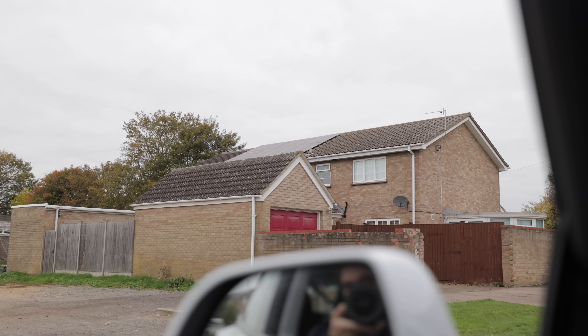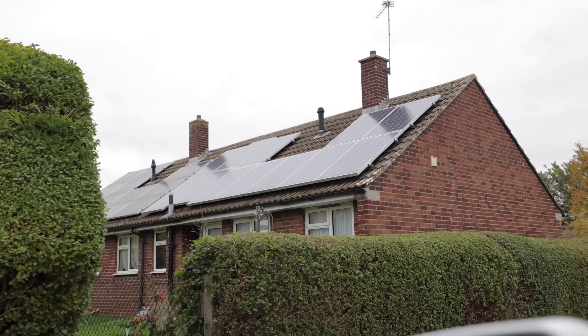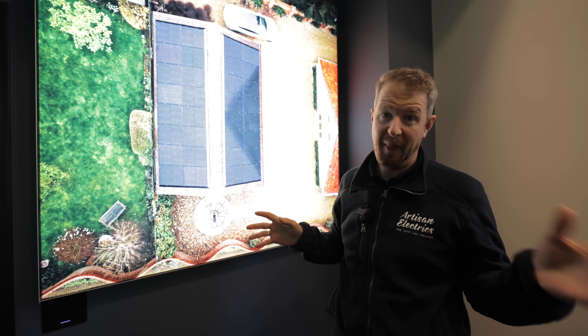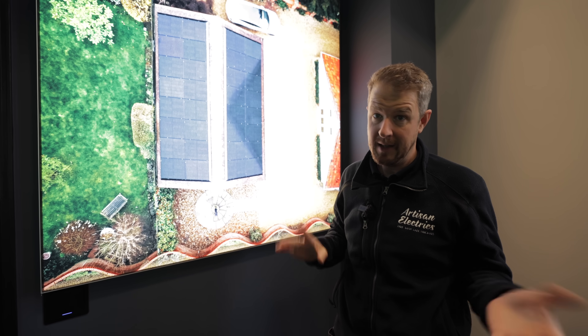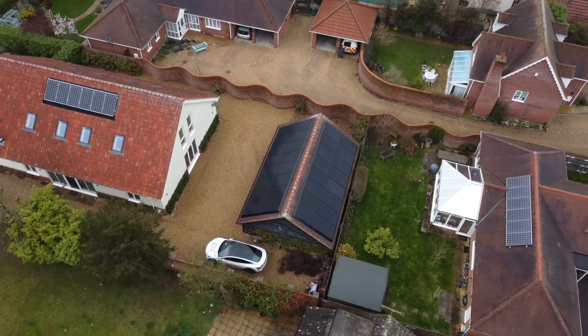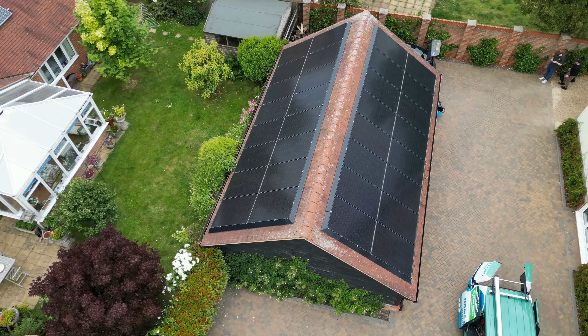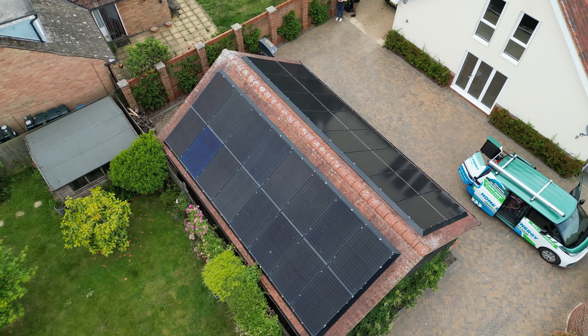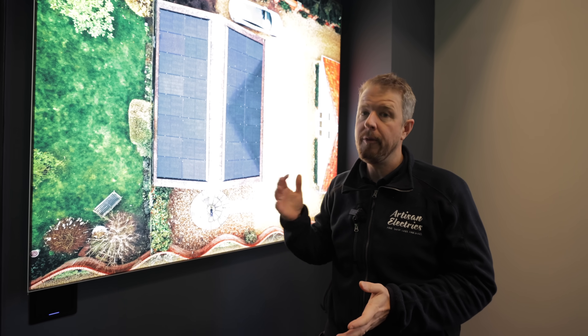Already from a short drive around we've seen lack of maintenance — systems absolutely encrusted in lichen since installation — poor cable management with cables just slung off the edge of the roof or in flexible conduit, and no bird protection whatsoever. Compare that to what a good solar install should look like: a neatly laid-out array, correct borders around the edges of the panels, proper bird protection, no cables slung across the roof, and panels regularly cleaned — all the result of a top quality install followed by good aftercare.